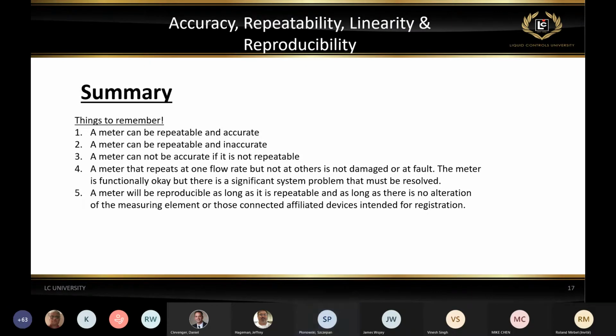If the meter repeats at one or two flow rates but doesn't repeat at other flow rates, there's nothing wrong with the meter. The meter is functioning fine, but there's some significant system issue that needs to be addressed. Again, often the meter is a messenger of what's going on in the system. If we have an issue with pump size or anything else, or air in the system, whatever the problem is, the meter will indicate that. And the last one is reproducibility. Again, that's repeatability in testing across maybe multiple days. As long as there are no changes made to the system, to the meter, or any devices related to registration, the reproducibility will be there as long as the meter is repeatable.